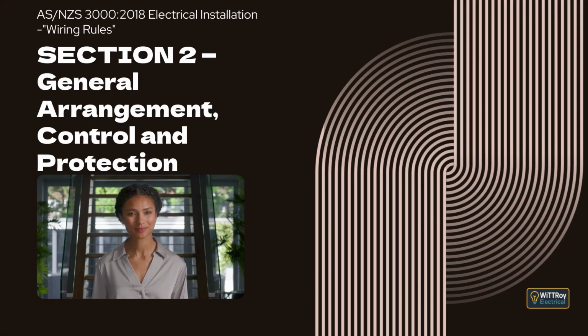Clause 2.2.1.2 Origin of submains and final subcircuits. This clause is simple. Every submain and every final subcircuit must start at one switchboard. All the live conductors for that circuit must come from the same place. This keeps circuits clearly identified, easy to isolate, and easy to test.